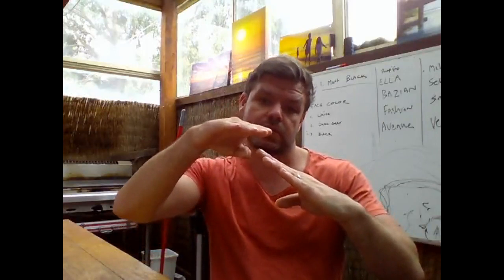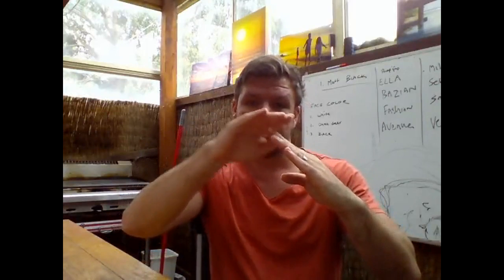Now, with that therapy, it's fixed to a set level, and generally what we have is what we call a ramp period in the beginning. So we generally ramp up, depending on where that level is, we ramp the pressure up gradually over a set amount of time, which you can alter. Generally, a good time frame is 20 to 30 minutes. Maybe, if it takes you longer to fall asleep, you could put it up to sort of 45. But that's the general time frame. And the pressure gradually goes up automatically until it hits a set rate of pressure. And once it hits that set rate of pressure, it will then stay at that set level.